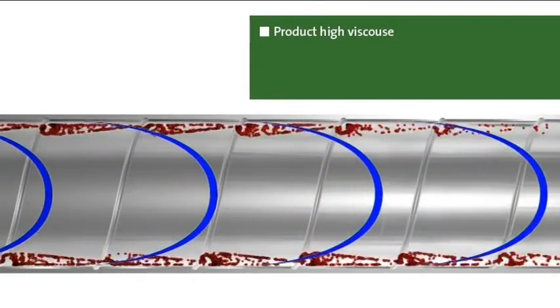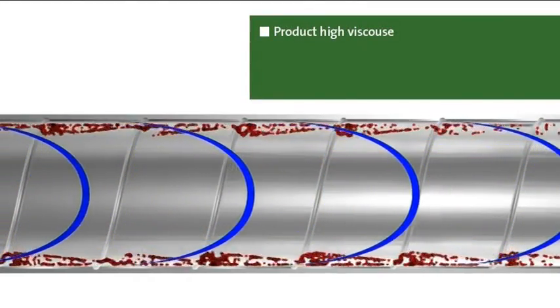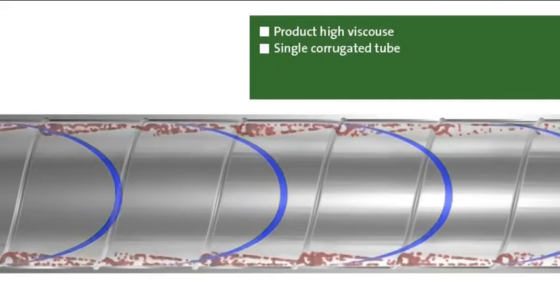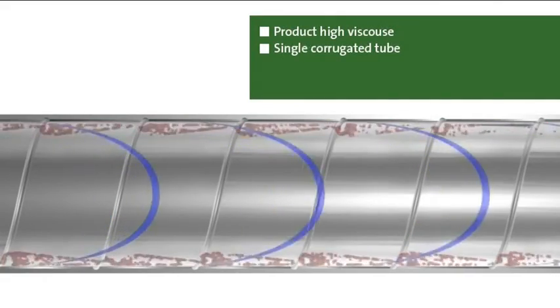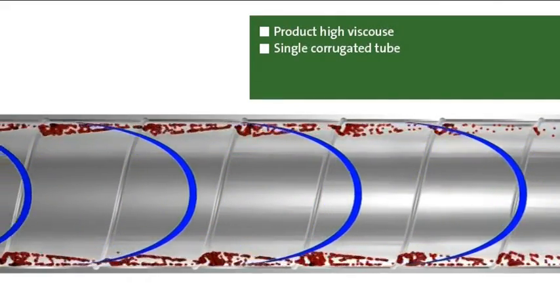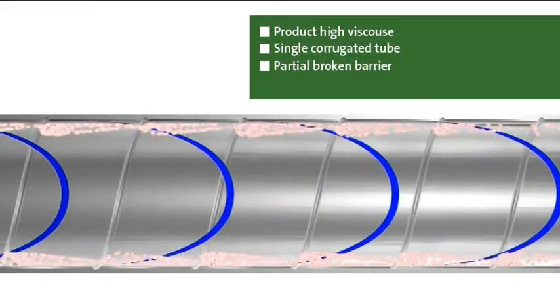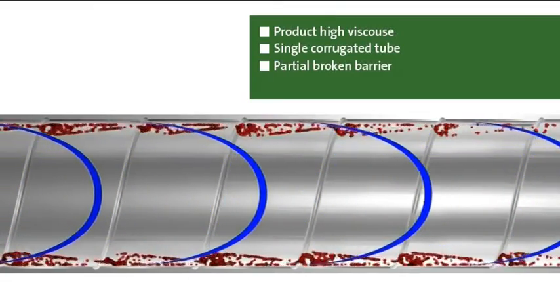Now we're looking at a high-viscous product in a single corrugated tube. The design of this tube causes the laminar layer to break up, thus producing a moderate heat transfer because the turbulences are not strong enough.